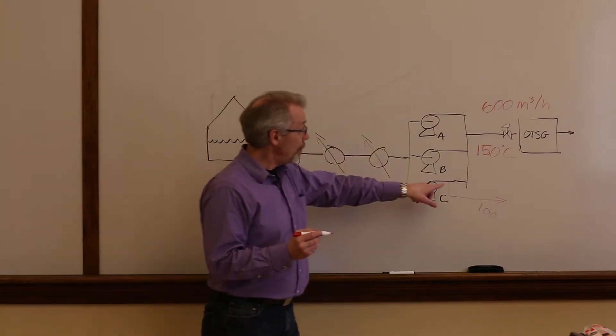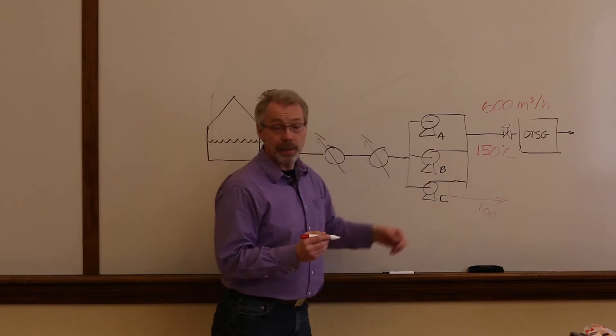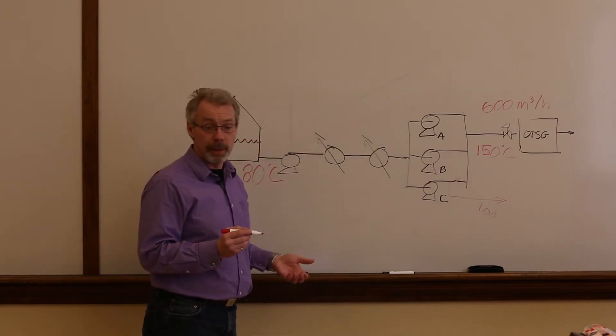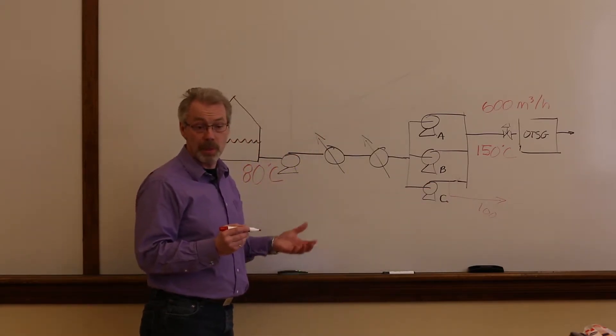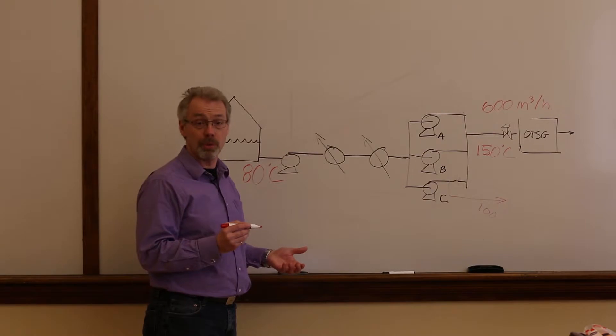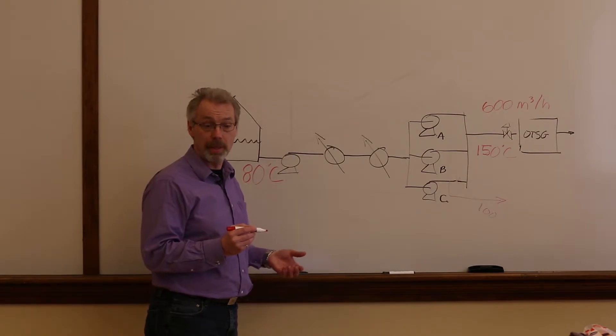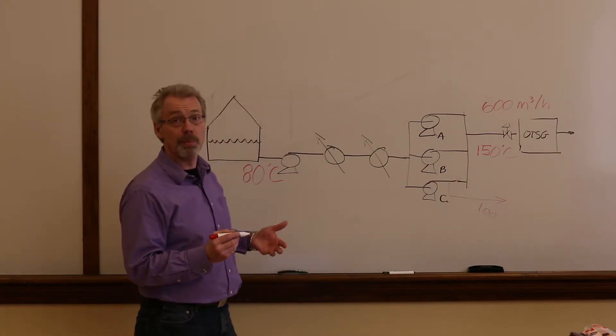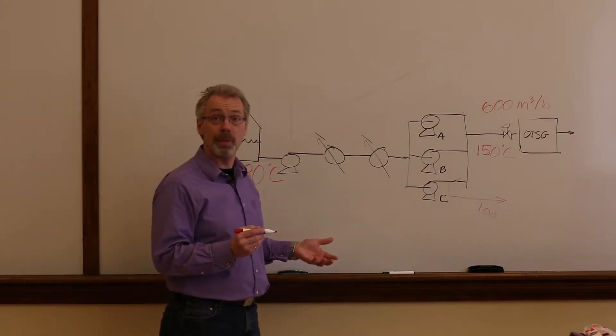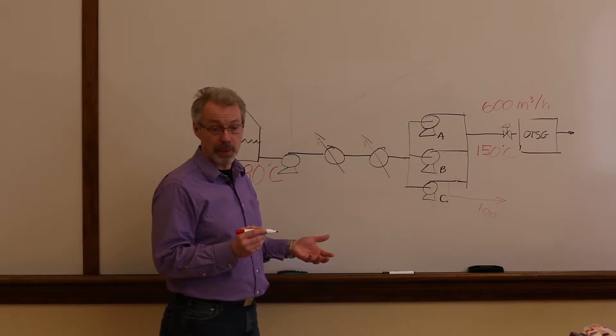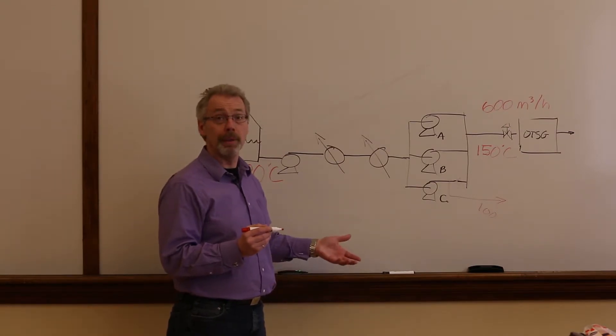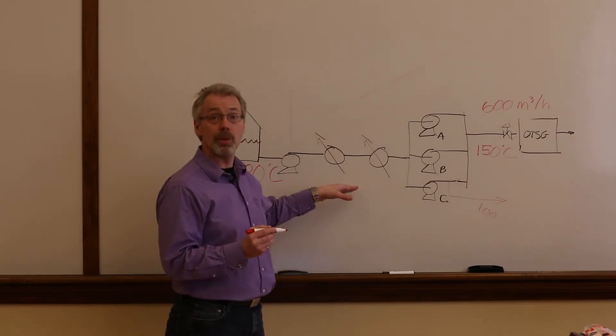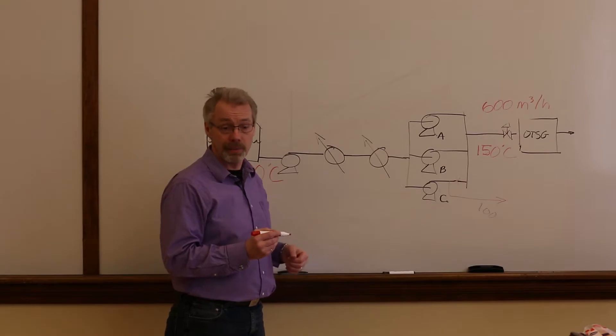Then, the pump is gradually cut into the header. The flow rate through the pump gradually increases and the minimum flow control is no longer needed. The total flow rate through all of the pumps drops to 600 cubic metres an hour, and we are back to the water gaining 70 degrees across the heat recovery section.